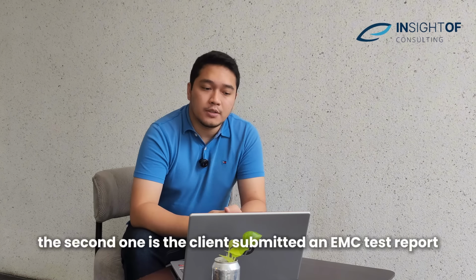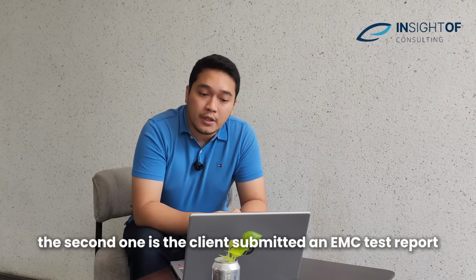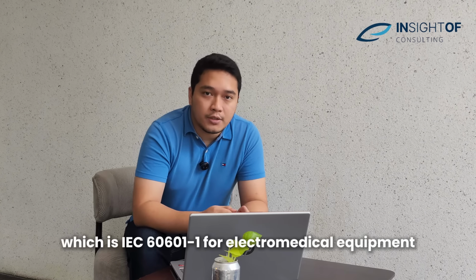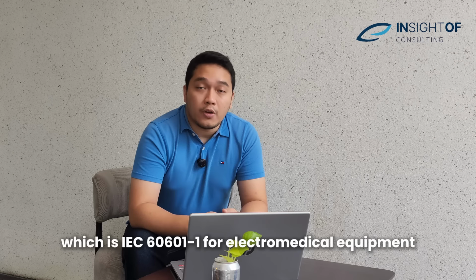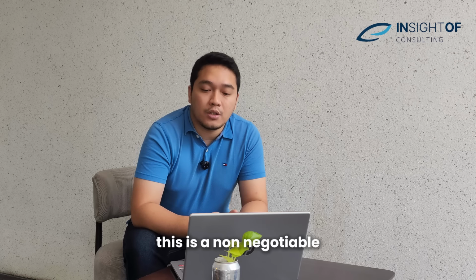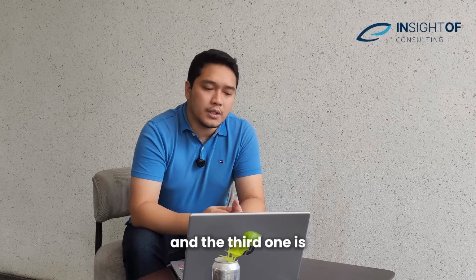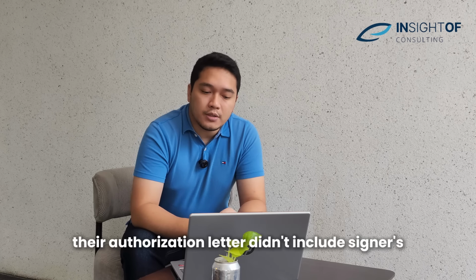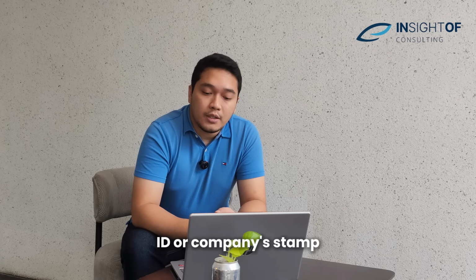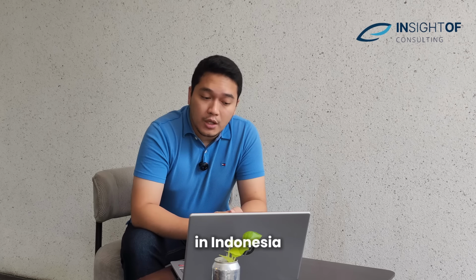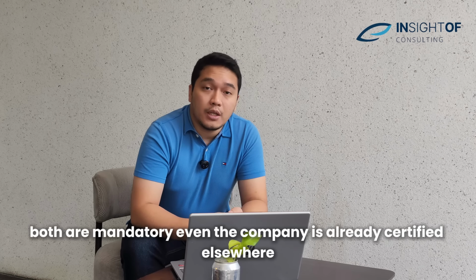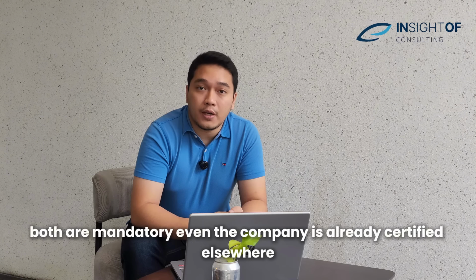The second one is the client submitted an EMC test report, but not one for IEC 60601-1. For electromedical equipment, this is non-negotiable. The third one is their authorization letter didn't include a signer's ID or company stamp. In Indonesia, both are mandatory, even if the company is already certified elsewhere.